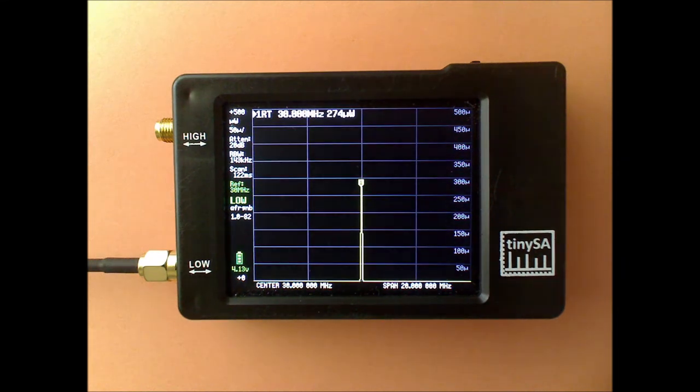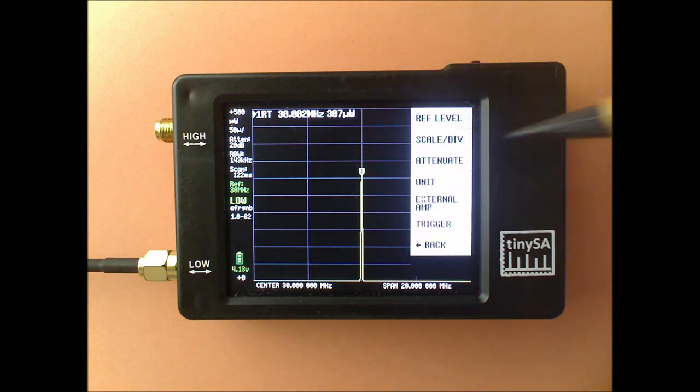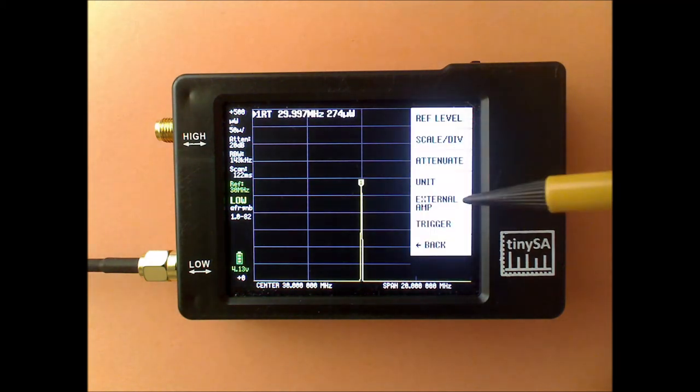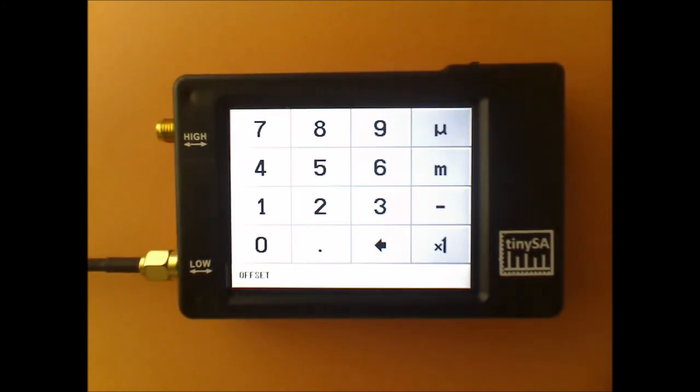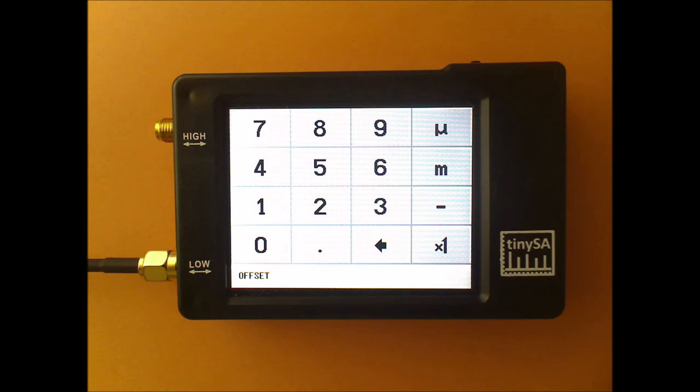Sometimes you want to measure very strong or very weak signal sources. And for that the external amp menu option is interesting. It allows you to specify the external attenuation or external amplification that has been applied to the signal. It's a known amplification or known attenuation.